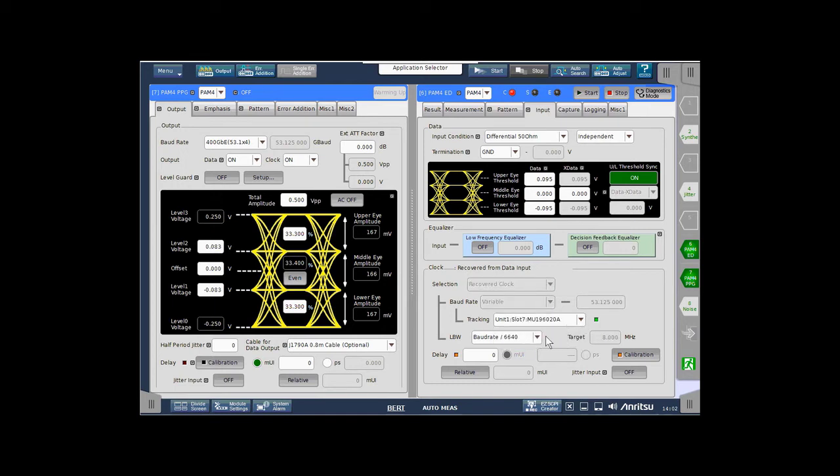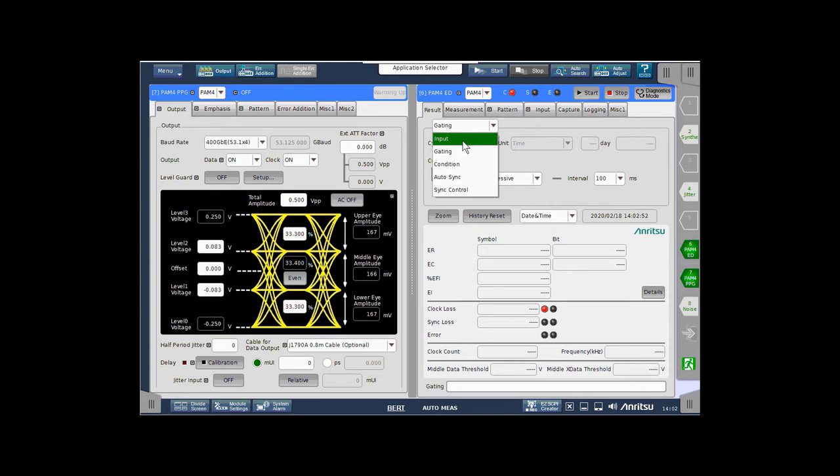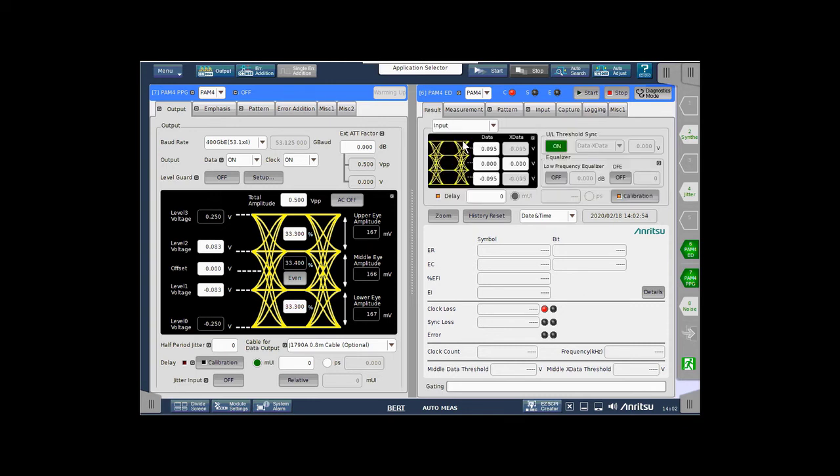That way, I never have to change the error detector clock frequency. And then we'll jump back to the result tab. And what I like to look at is the input settings. That way, I could watch my input thresholds change as we initiate an auto search.